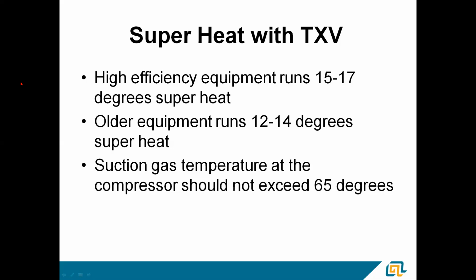This is why superheat's important. If you get up in that 60, 65 degree range in suction gas, you're not going to have enough cooling gas for that compressor. Compressor's going to run hot. And it's funny, as your suction gas temperature goes up, the gas becomes less dense. The compressor has to work harder to compress it, and you'll get an elevated discharge temperature. And in the long run, you'll be putting a lot of premature wear on that compressor.